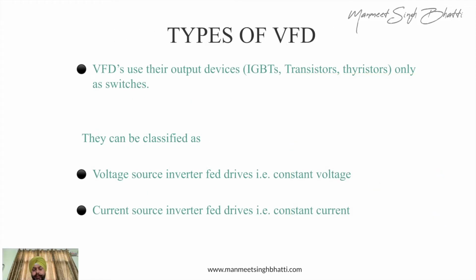So what the VFD does is, at the output, it has IGBTs or thyristors or transistors. Basically these are the components of the VFDs which convert your AC to DC and from the DC again to AC. These are switching devices, basically on and off devices. So you get power sometimes on, sometimes off, and based on that we are able to get a proper frequency. Now these are also used to do two types of control. VFD can also control the output voltage, and VFD can also control the output current. So these kinds of things you can also do.